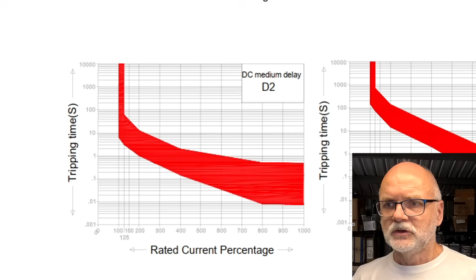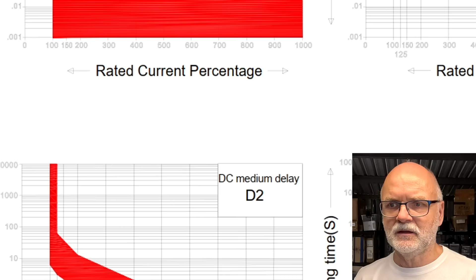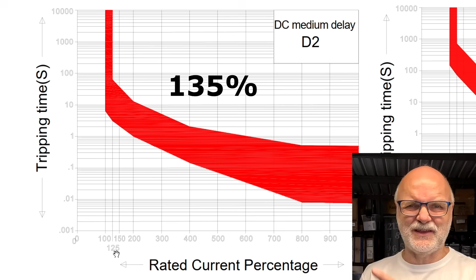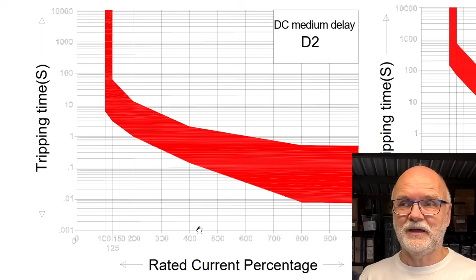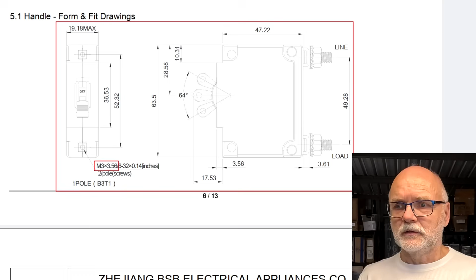Let me zoom in here a little bit so we can see something. All right, we've got the tripping time here on the y-axis in seconds and the rated current in percentage. So 100% means 200 amps. At 200 amps, it says here around 8 seconds or so until the breaker trips. And the sticker said something about 270 amps, which is maybe like 150% on the screen, and then we will trip at around 2 seconds. So that's actually not too bad. And of course, the higher the current is, the faster it will trip.